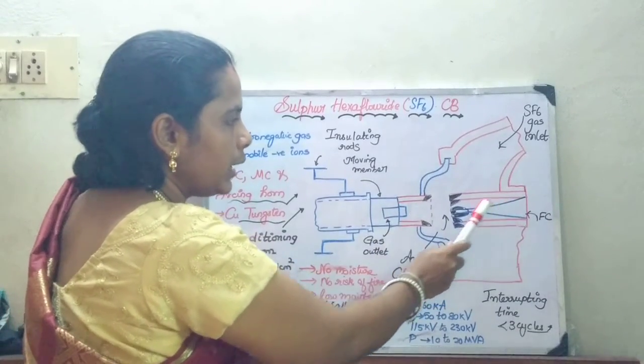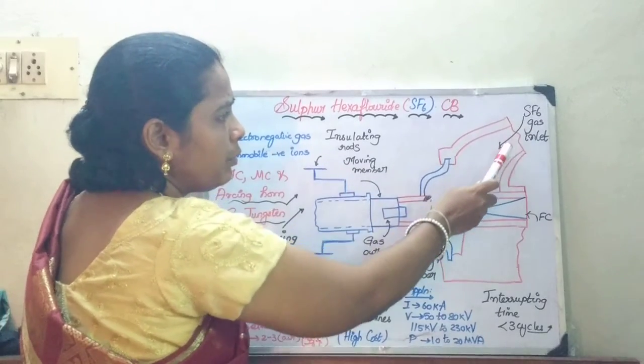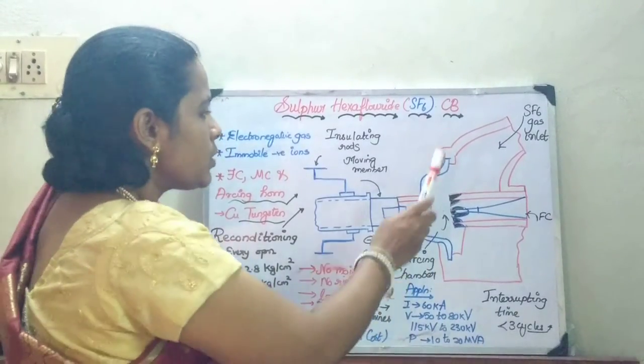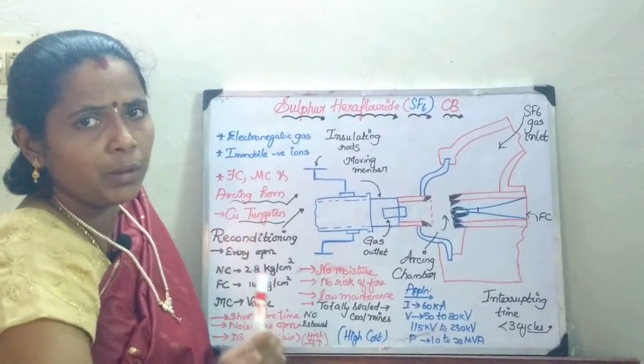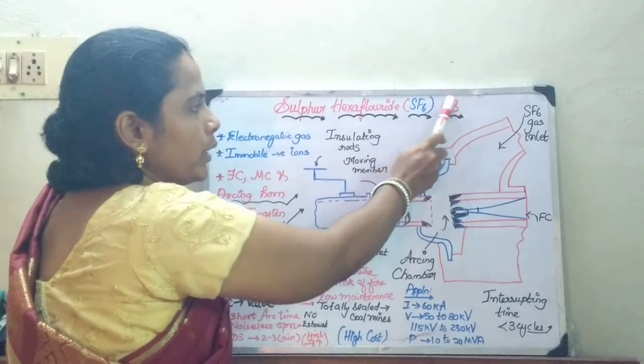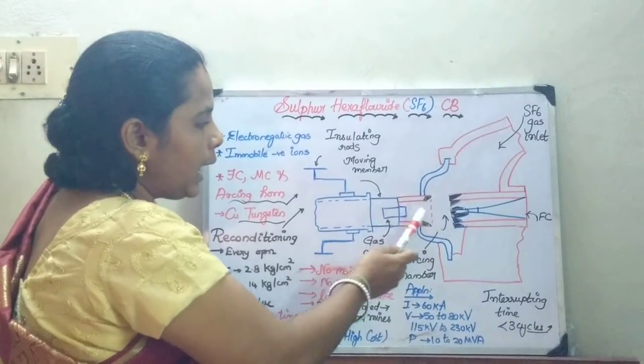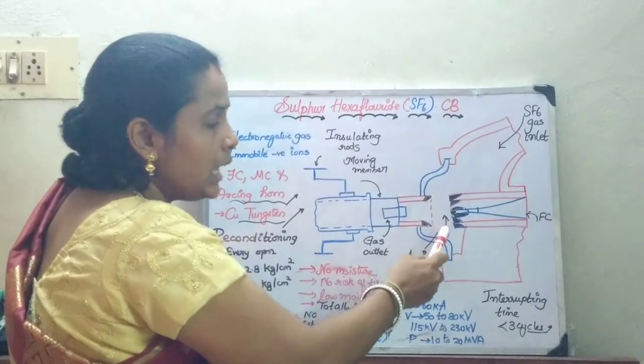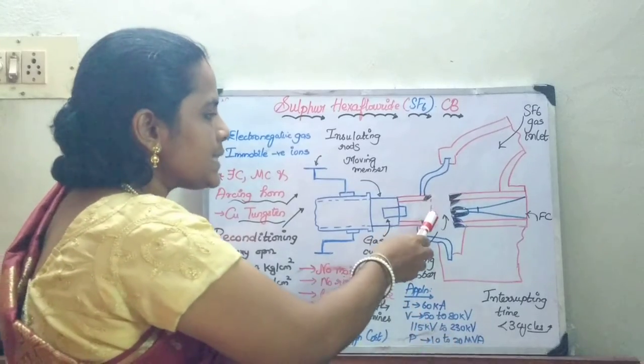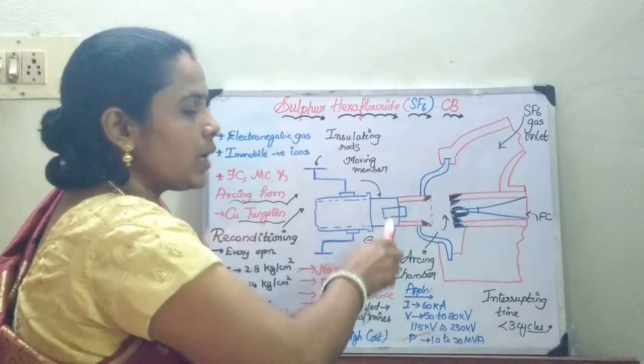Moving on to the operation: you have a moving contact, a fixed contact, and an arcing horn for splitting the arcs. Whenever a fault occurs, the SF6 gas is let into the arcing chamber. The moving contact is associated with a valve mechanism, so whenever under a fault the moving contact is moved apart, it is synchronized with the amount of gas inlet. As the contact is pulled apart under the fault condition, the gas is let inside. This electronegative gas absorbs all the ions and converts them into immobile ions, helping build up the dielectric strength at a faster rate, thereby quenching the arc at the earliest time.